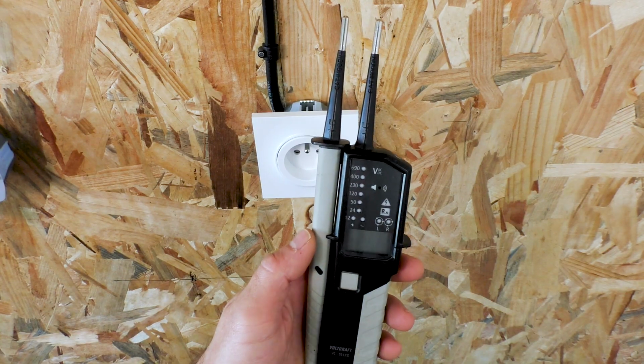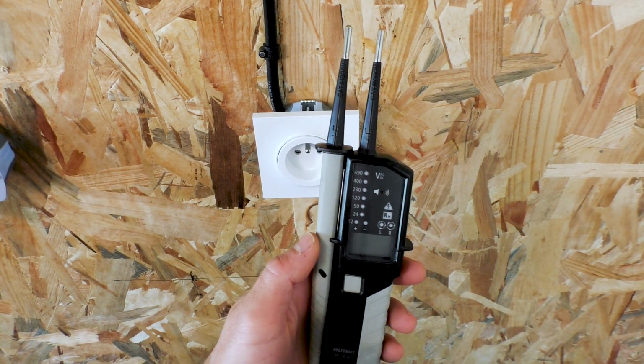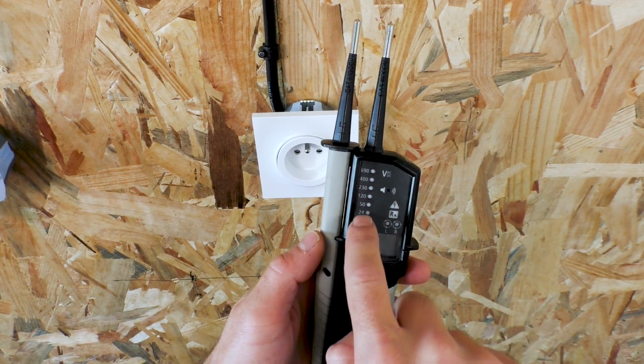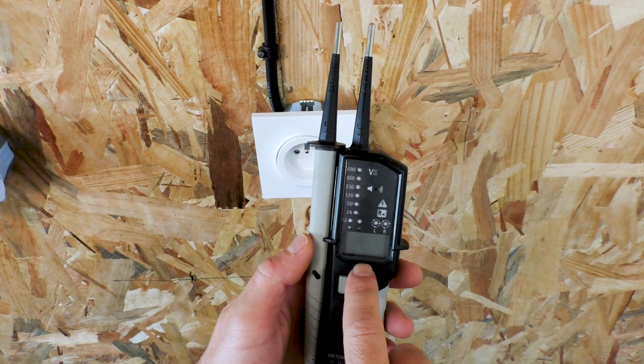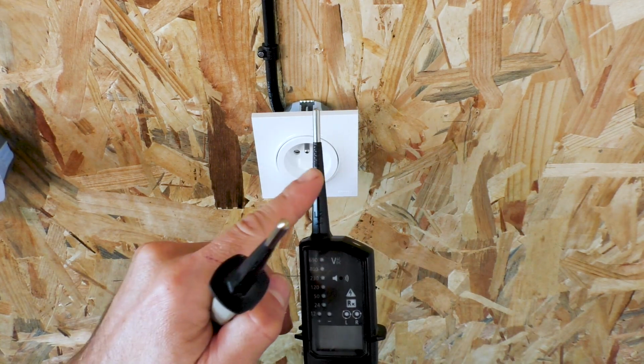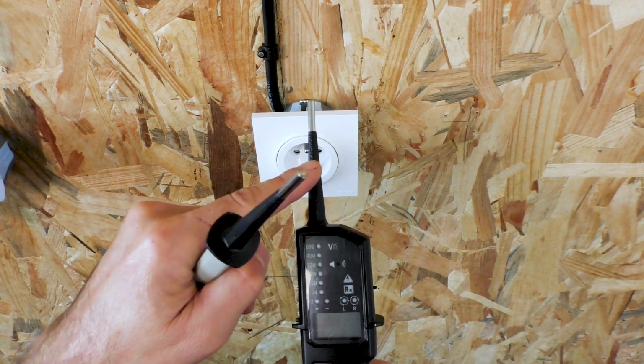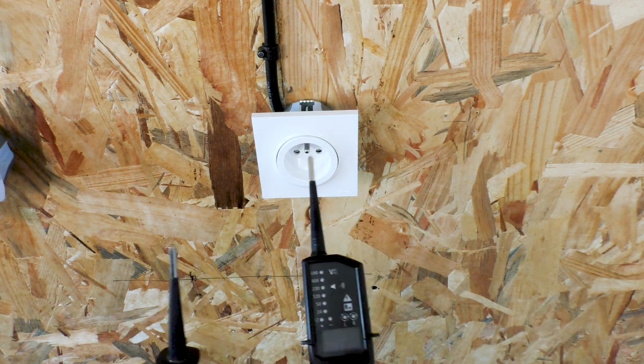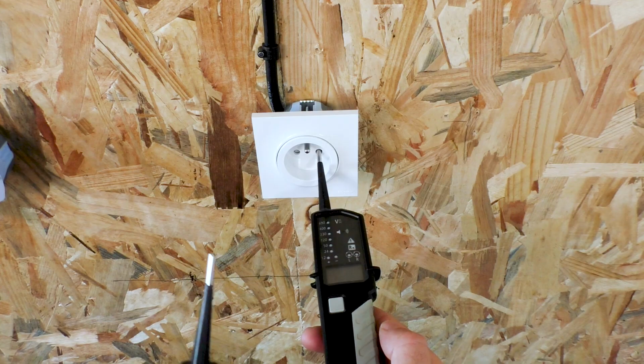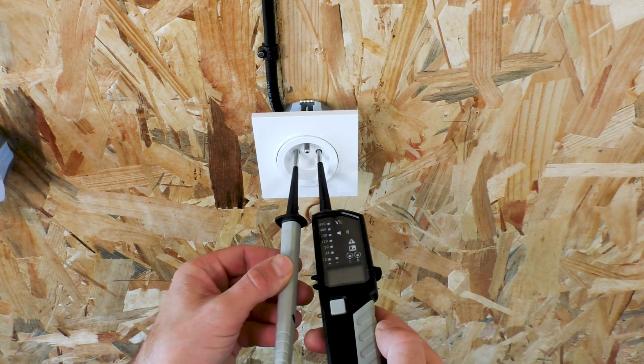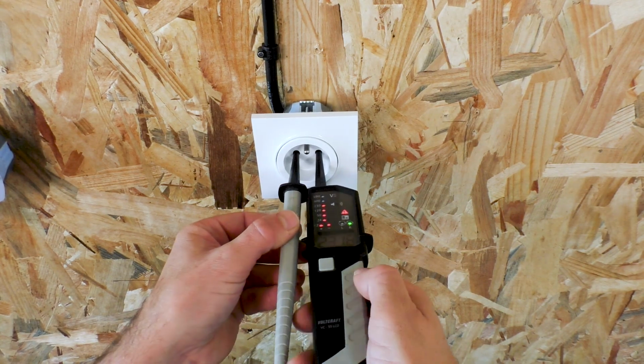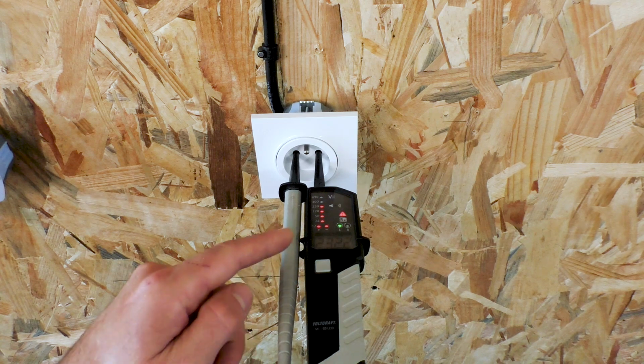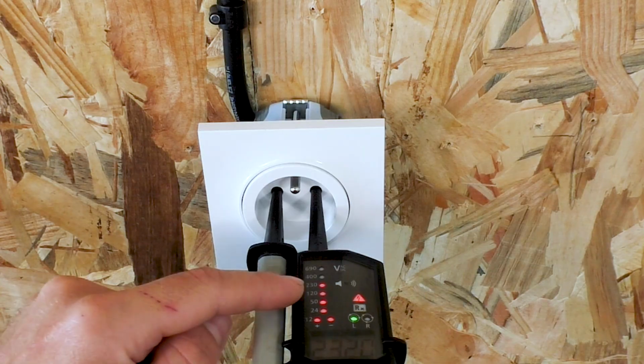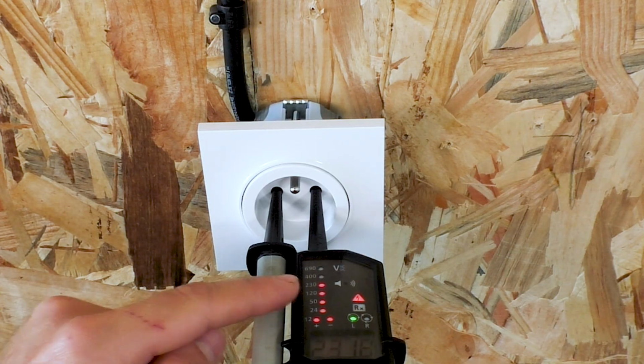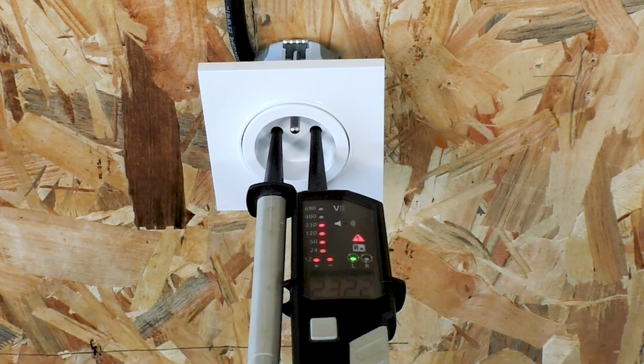Next up, the voltage tester with probes. The voltage tester with probes will show you a voltage range by illuminating different lamps, and this model will also show you an exact voltage on the screen here. You insert the positive probe, the one that is on the tester itself, into a live slot of your socket, and a negative probe into a neutral slot. Now it starts to make this ringing sound. It shows you a voltage range 230 here in Europe, and also an exact voltage on the screen.